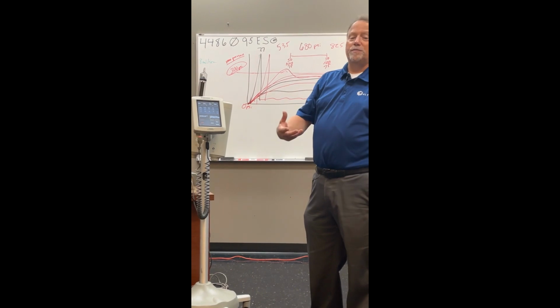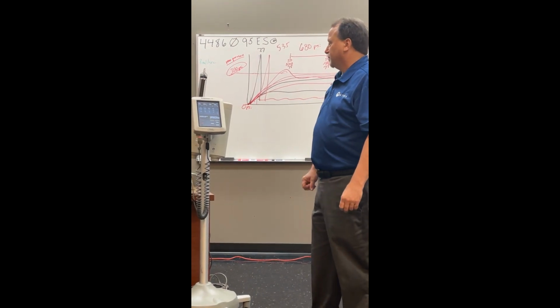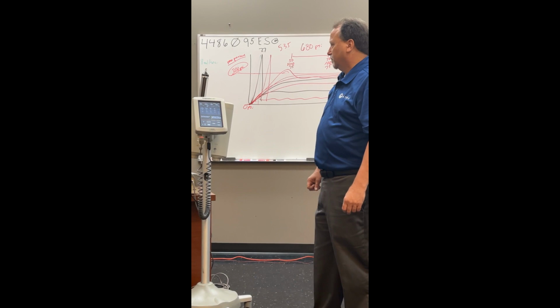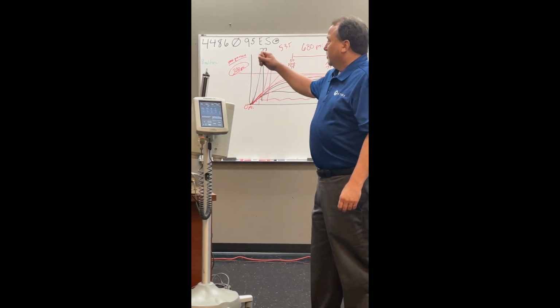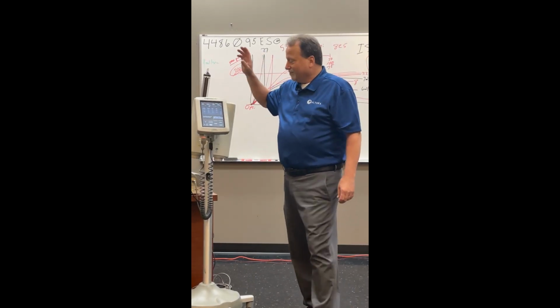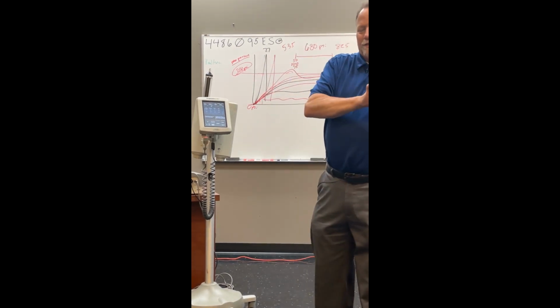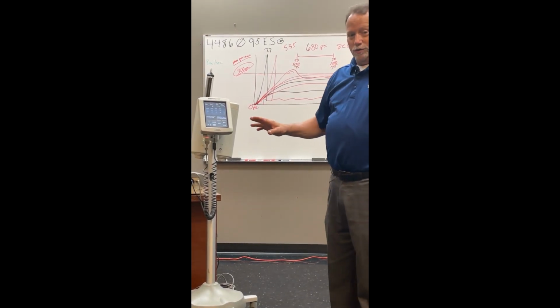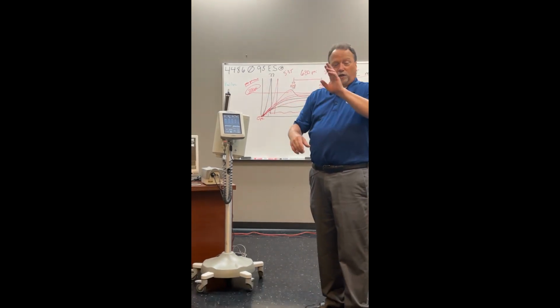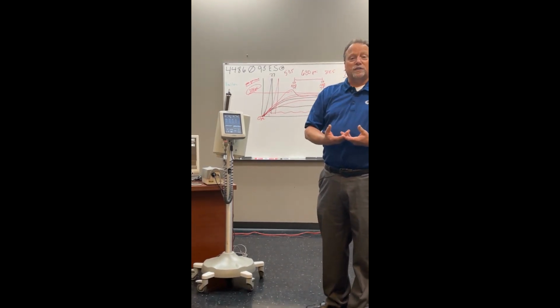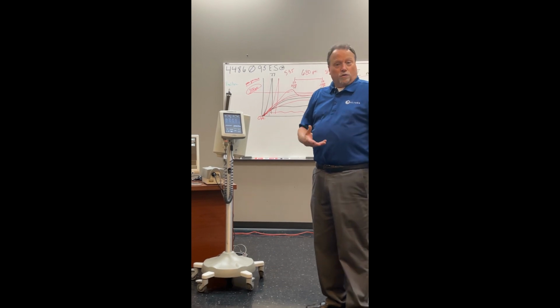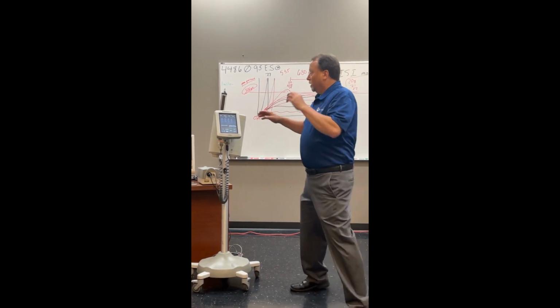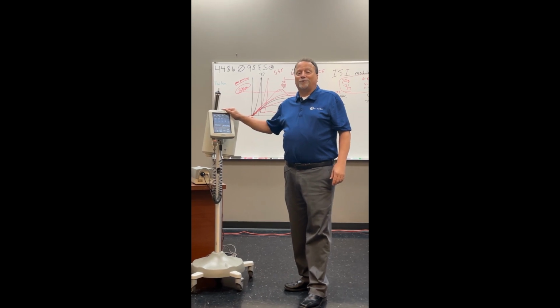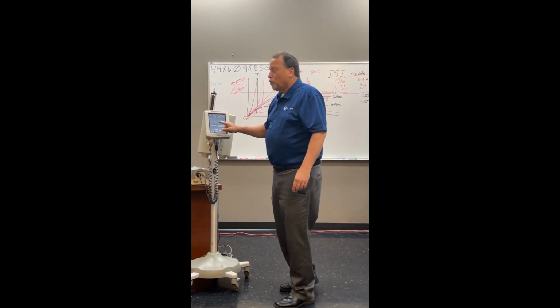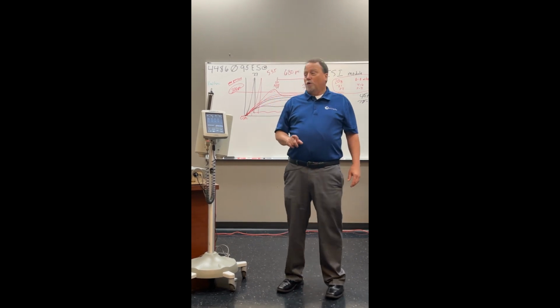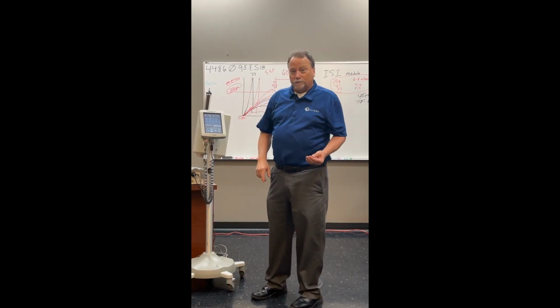So it's basically homing the piston is what it's doing. Okay, so now it's ready to be filled. Like the Stellant, this has an auto load where you put the protocol in, you hit auto load, and it fills up the contrast and saline to the needed volume for that protocol. These injectors call it something different. It's called protocol fill, or on the older version, it's called protofill.